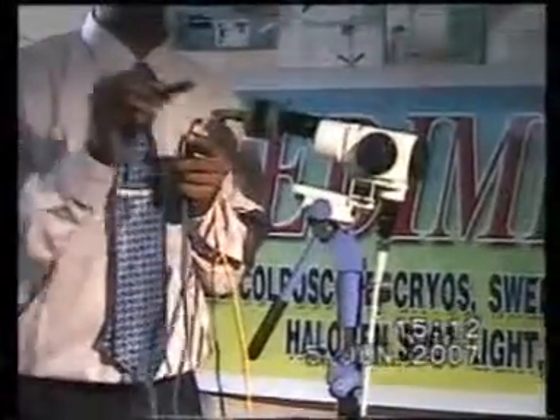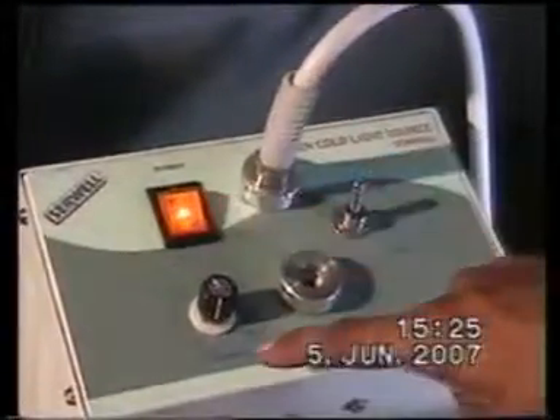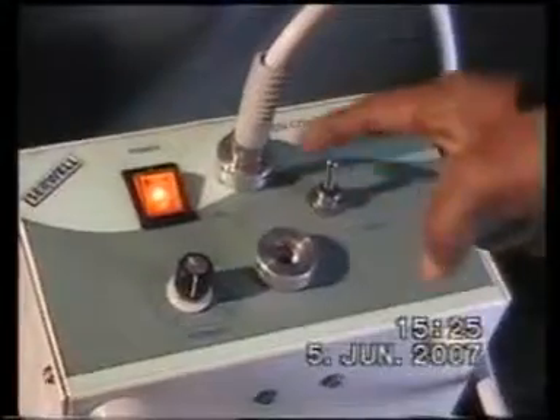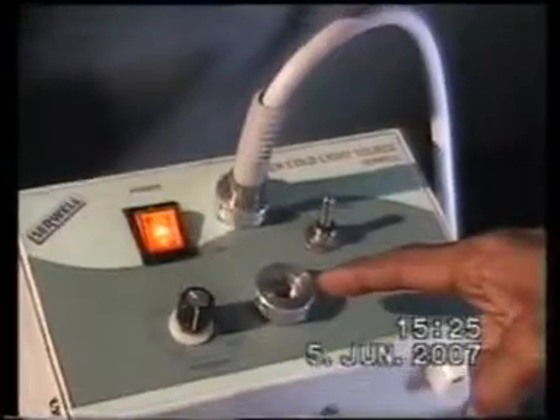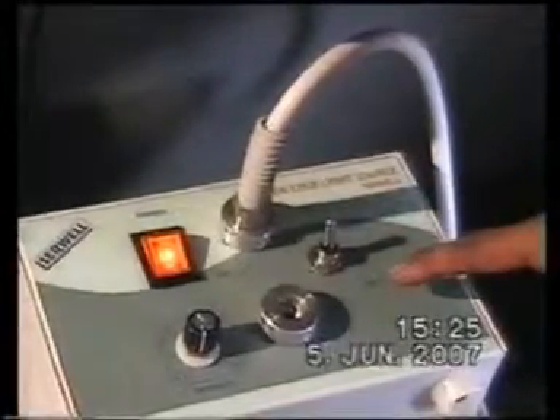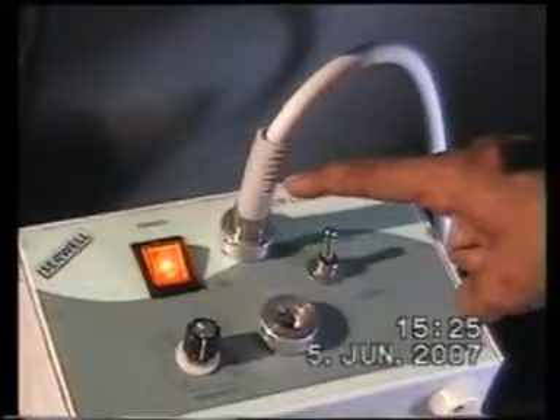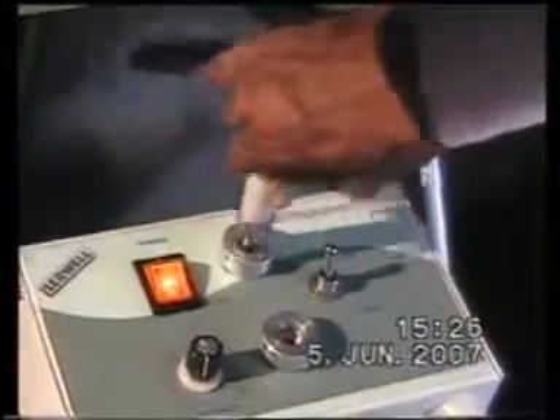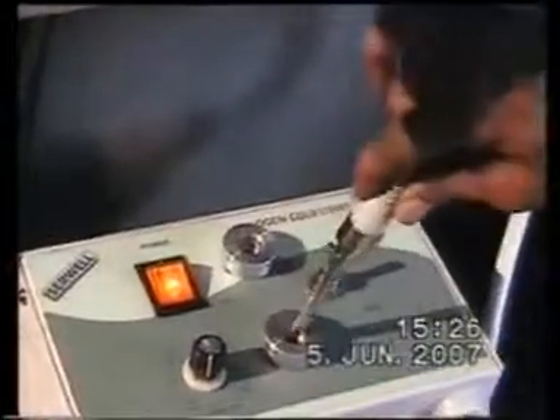Blue wire is to be connected to the TV video in. Light source wire is to be plugged here. This plug point is from the camera adapter. From the camera, the adapter wire is coming like this and it is connected here. Now, this is the light source power. This is the intensity control of the light source. These two ports are for fiber optic cable. There are two bulbs, lamp 1 and lamp 2. When the first bulb goes out of order, remove the fiber optic cable from port 1, then insert it into port 2.